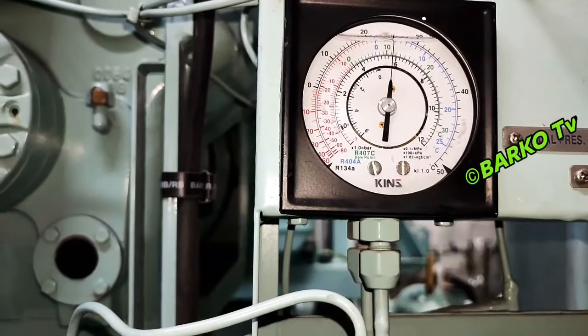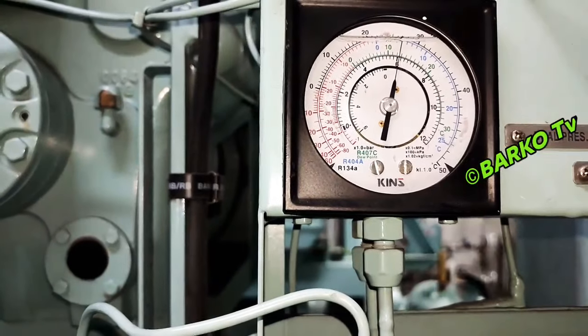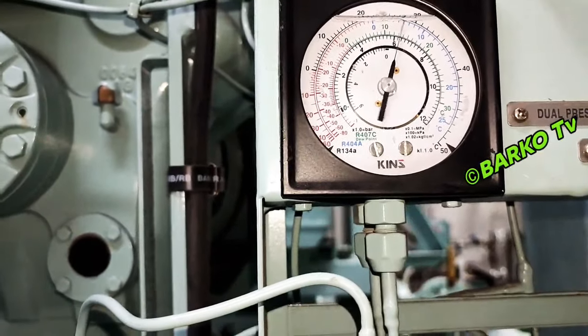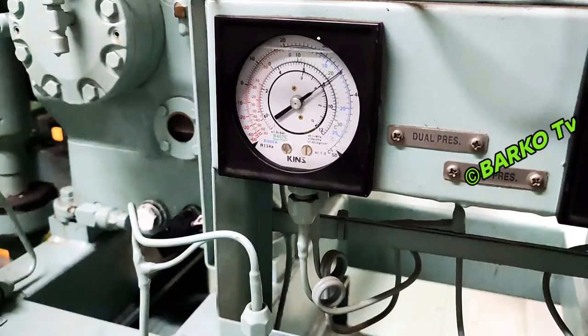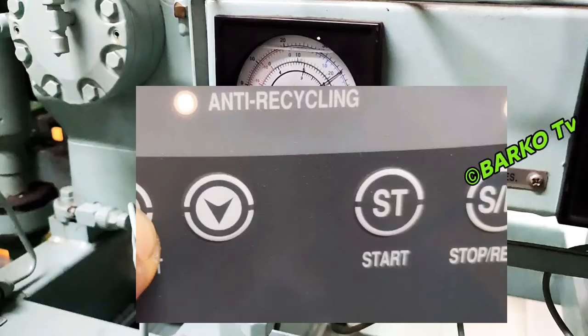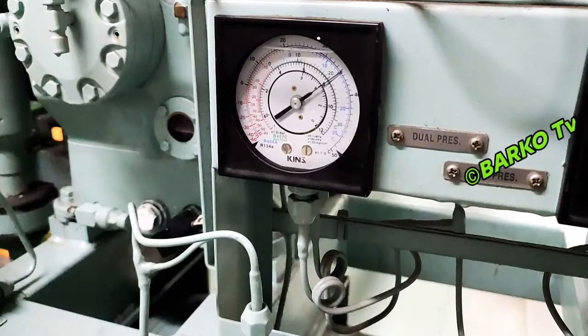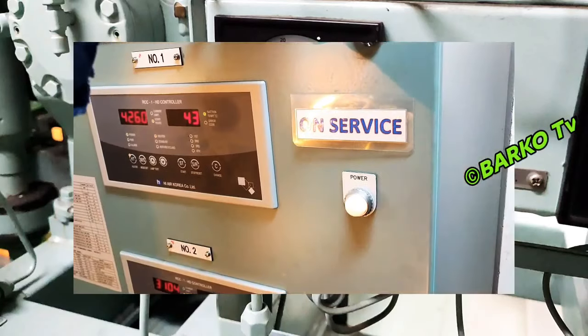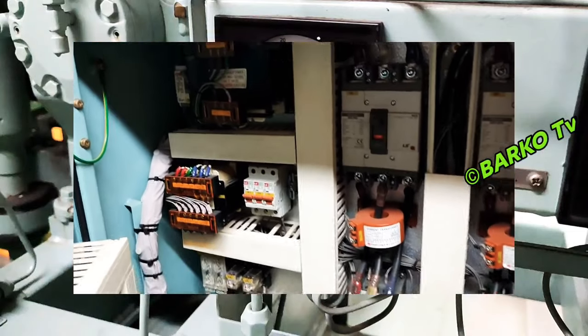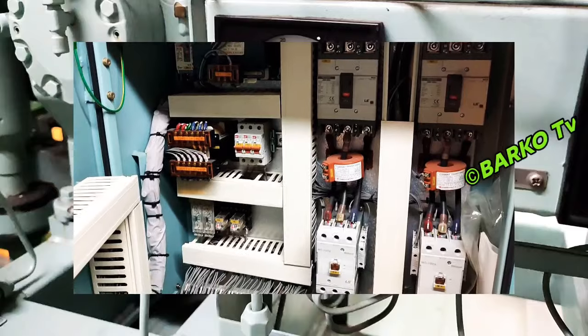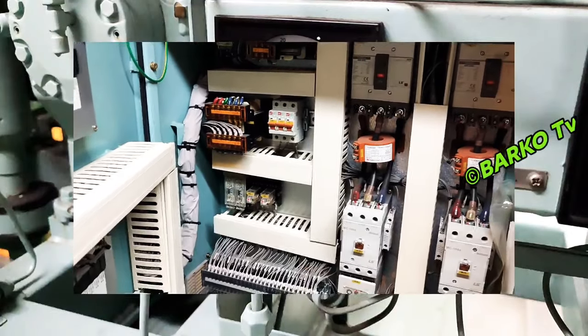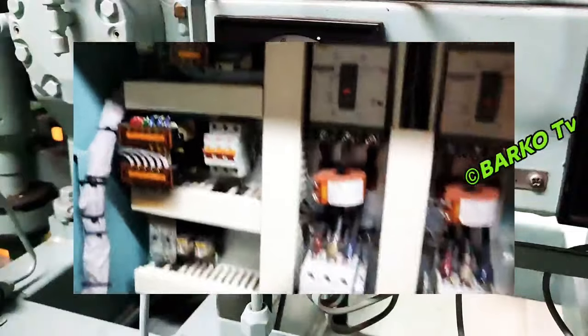After that, you wait for the compressor to run automatically, but you need to check if the anti-recycling time is triggered. Once the low pressure is triggered, the compressor program automatically activates the anti-recycling time. Our recycling time is almost 20 minutes. Another system is 30 minutes. But if you need to run this compressor, press stop and then turn off the control breaker inside. Then turn on. After that, the recycling time is reset.